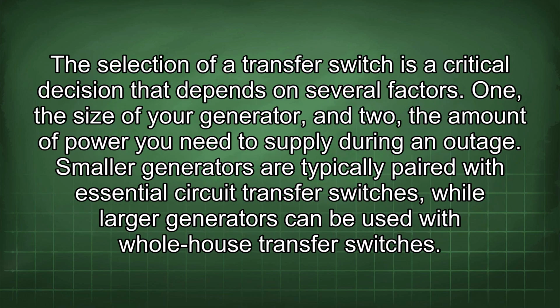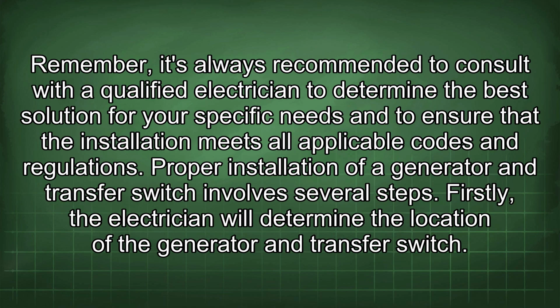The selection of a transfer switch is a critical decision that depends on several factors. 1. The size of your generator, and 2. The amount of power you need to supply during an outage. Smaller generators are typically paired with essential circuit transfer switches, while larger generators can be used with whole house transfer switches. Remember, it's always recommended to consult with a qualified electrician to determine the best solution for your specific needs and to ensure that the installation meets all applicable codes and regulations.